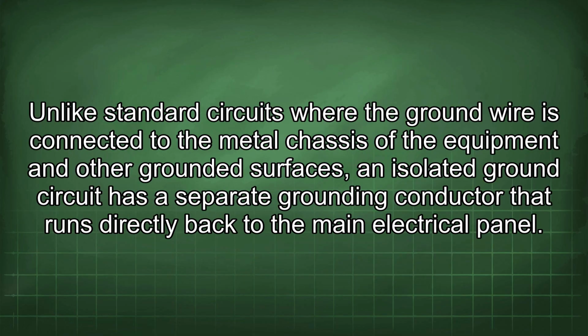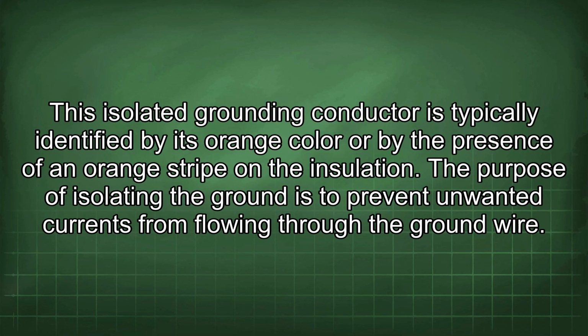Unlike standard circuits where the ground wire is connected to the metal chassis of the equipment and other grounded surfaces, an isolated ground circuit has a separate grounding conductor that runs directly back to the main electrical panel. This isolated grounding conductor is typically identified by its orange color or by the presence of an orange stripe on the insulation. The purpose of isolating the ground is to prevent unwanted currents from flowing through the ground wire.